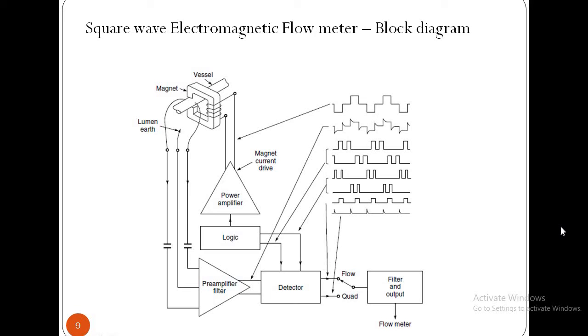The induced voltage picked up by the electrodes is given to a low noise differential amplifier through a capacitive coupling. The preamplifier must have a very high common mode rejection ratio and input impedance. A gating amplifier helps to remove spurious voltages generated during the magnetic current reversal.